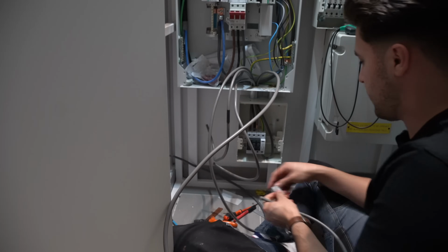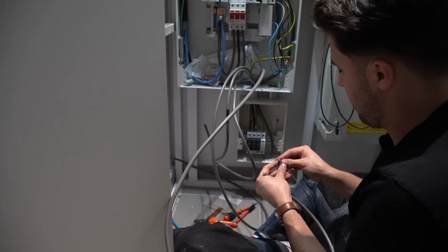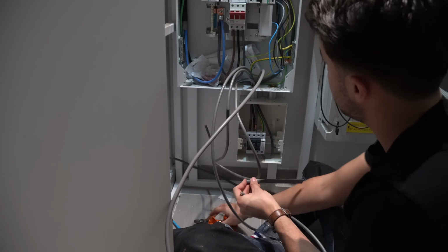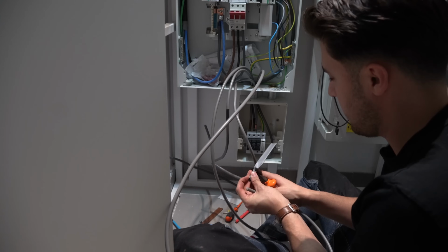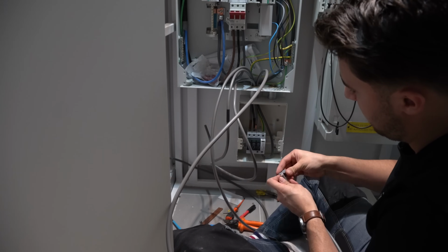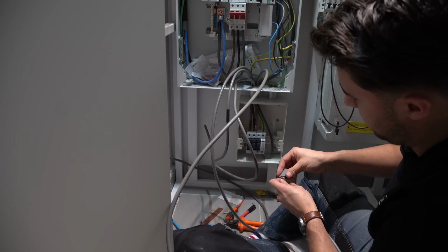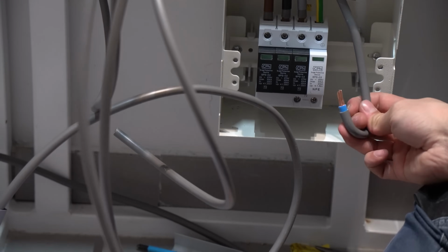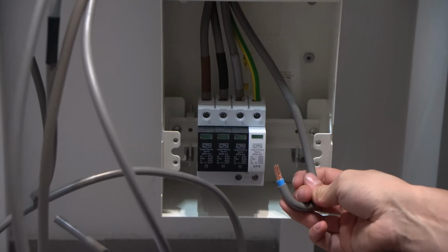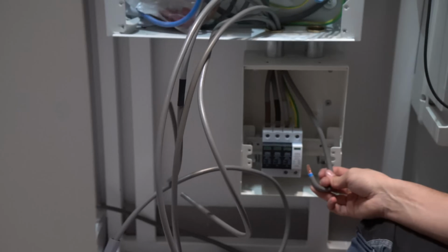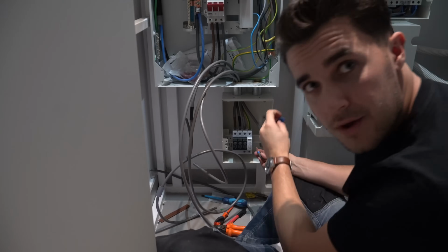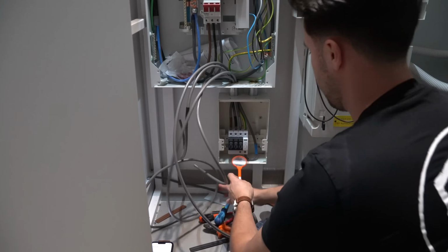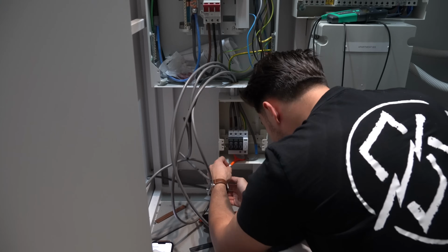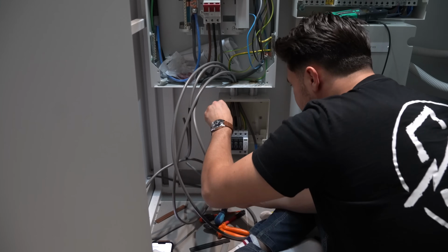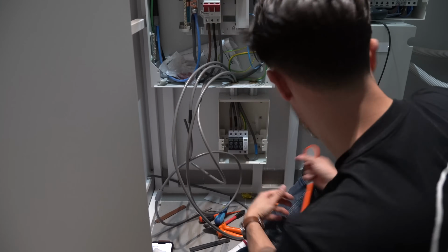Just fitting some heat shrink onto everything just to verify what it is. But what we've done is we've got a 63 amp C-curve breaker coming out of the three-phase board. That then feeds this surge protector. These cores are actually colored internally, if you look. They've got blue and all the different various colors, but I'm just using a bit of heat shrink just to make life easier for the next engineer to come. Just check on that connection back there to make sure it's all good. Double check yourself always. You're never too good to make a mistake.